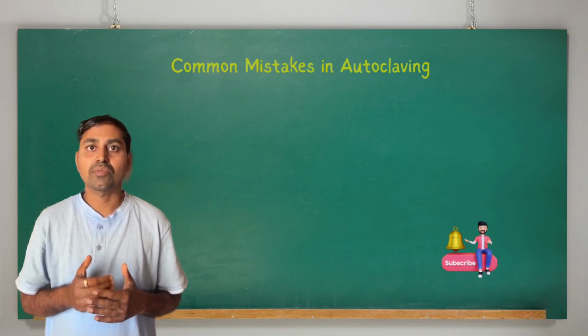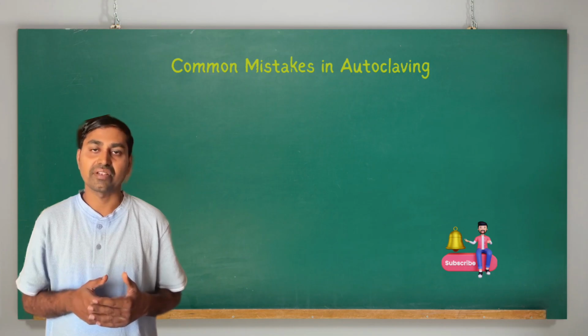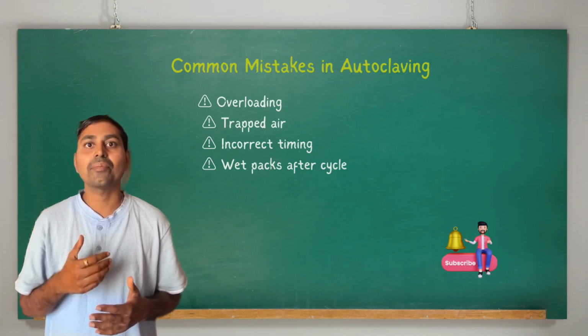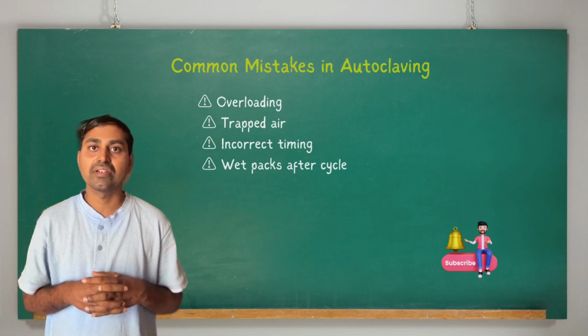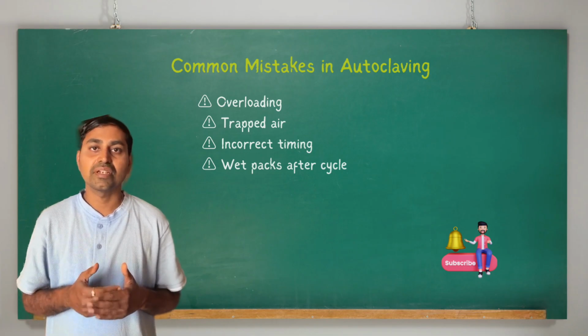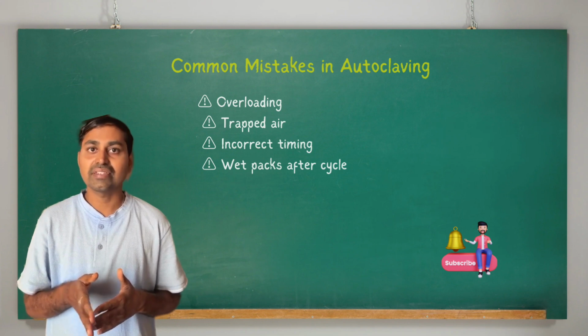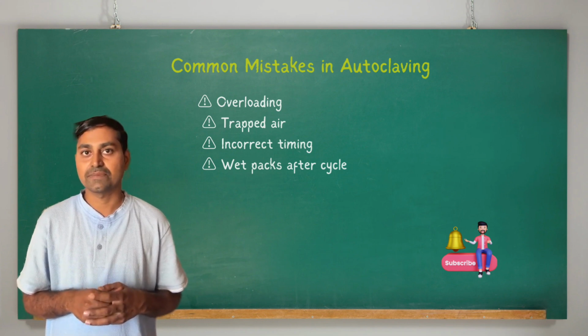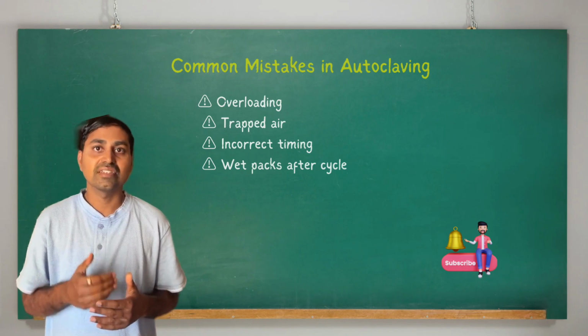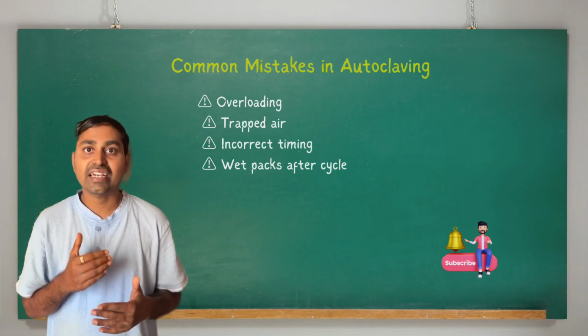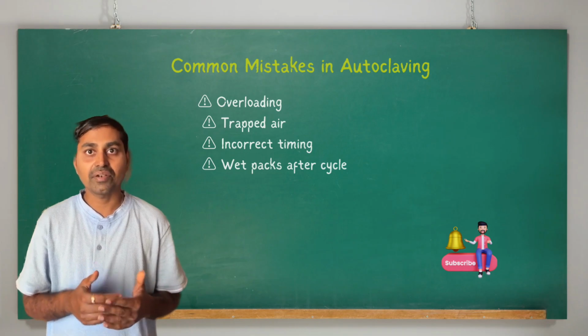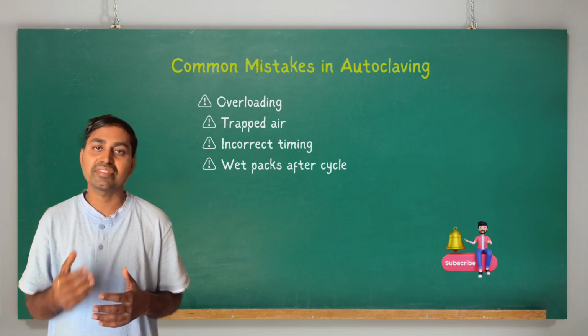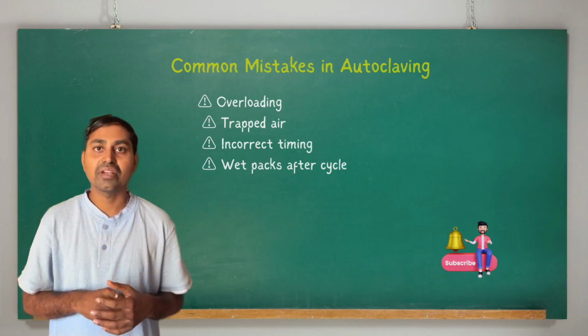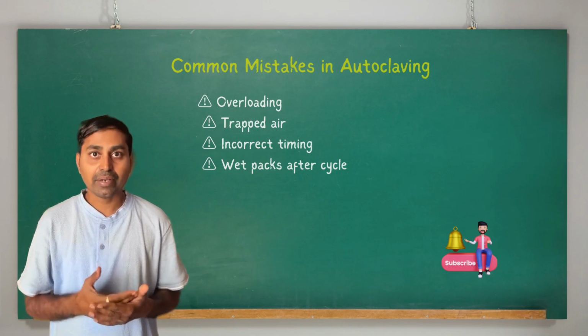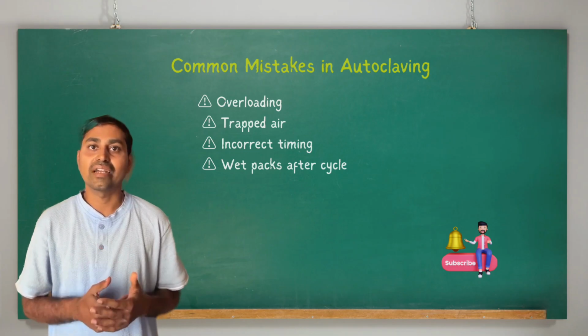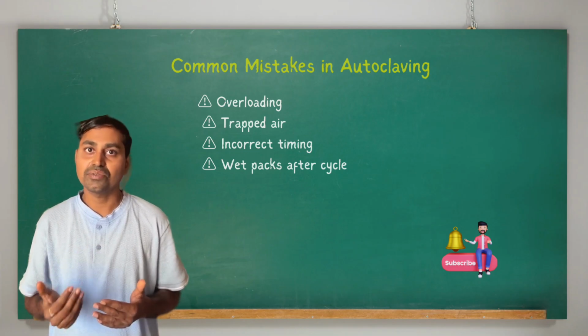Next we will see some common mistakes we make in autoclaving. First one is overloading. What happens if we overload the autoclave? It prevents the penetration of steam into the instruments, thereby sterilization will not be effective. Then trapped air reduces sterilization efficiency. Then incorrect timing. I told you 15 to 20 minutes for standard autoclaving. If we set 10 minutes or 5 minutes, there will be no effective sterilization. Then wet packs after the cycle can lead to contamination. If they are not dried, that again leads to contamination.